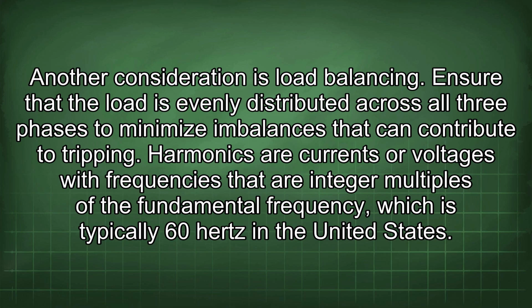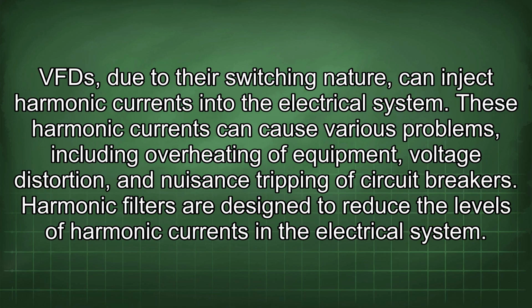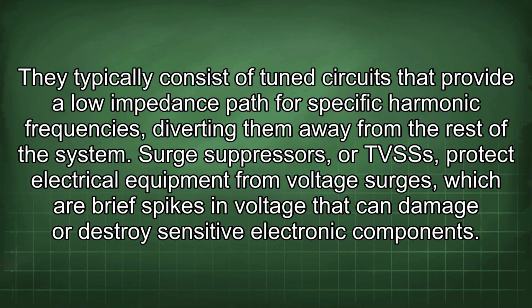Harmonics are currents or voltages with frequencies that are integer multiples of the fundamental frequency, which is typically 60 Hz in the United States. VFDs, due to their switching nature, can inject harmonic currents into the electrical system. These harmonic currents can cause various problems, including overheating of equipment, voltage distortion, and nuisance tripping of circuit breakers. Harmonic filters are designed to reduce the levels of harmonic currents in the electrical system. They typically consist of tuned circuits that provide a low impedance path for specific harmonic frequencies, diverting them away from the rest of the system.